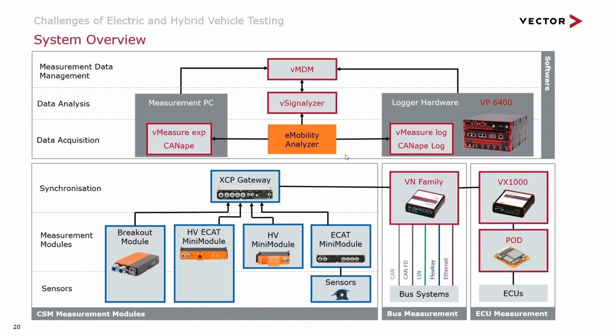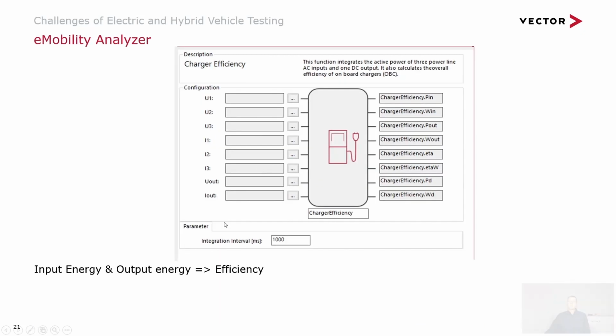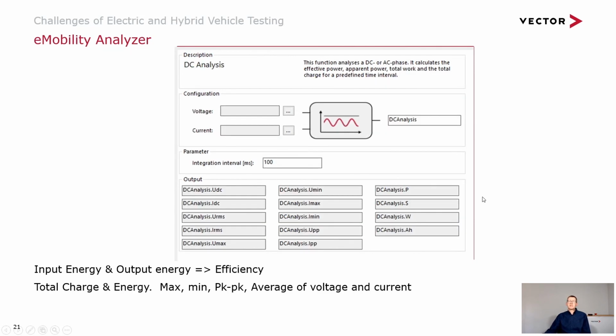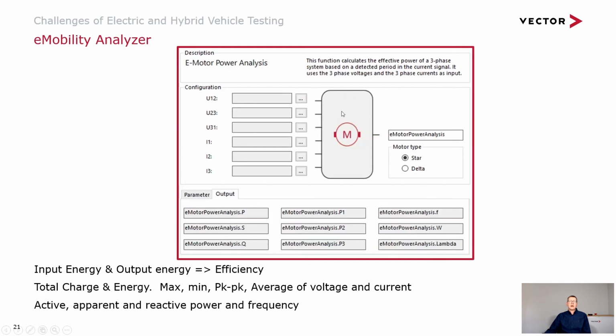So we can log our voltages and our currents with the hardware, we can feed it into the e-mobility analyzer, and then we have these block sets for calculating parameters. So our three-phase input into our charger and our DC output can be fed in, and we can calculate various energies and powers of the charger. We've got a DC analysis module, feed that into the inverter as DC, and then calculate charge and energy and power and various parameters. And then we've got another one for e-motor analysis. We have star and delta setup, three-phase in, and then we can calculate active, apparent, reactive power, frequencies. So it's a very powerful tool set for calculating on the fly or offline all of the parameters to analyze our test.